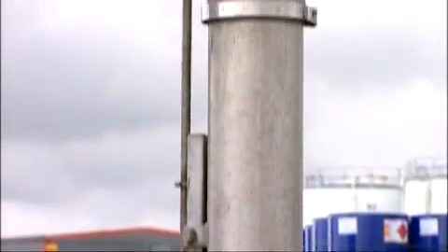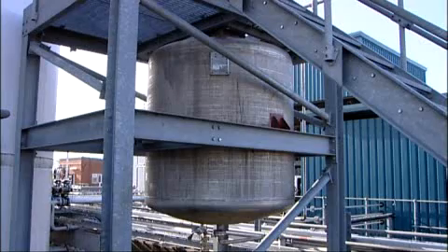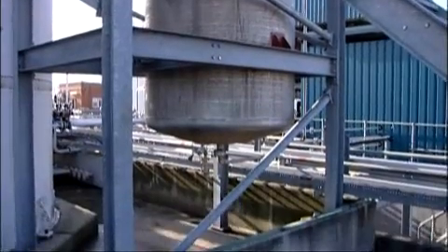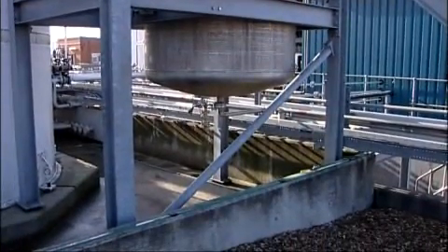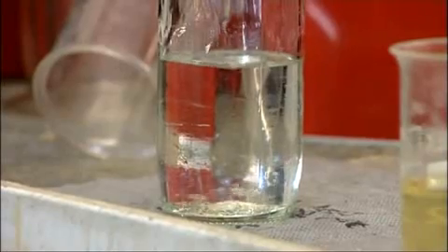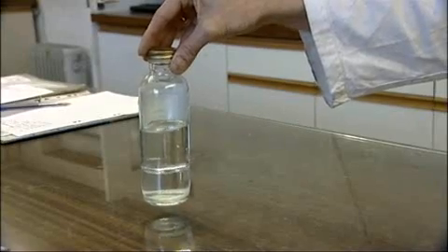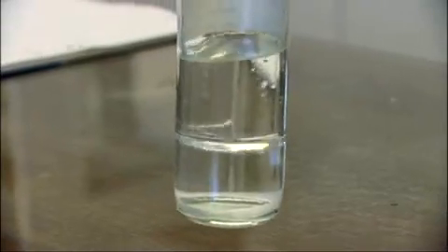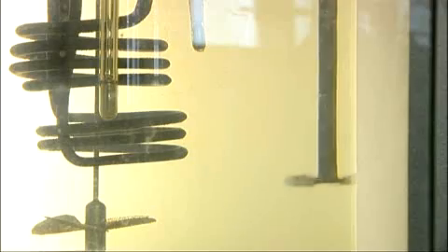Dispersing operations can be particularly hazardous in view of the extremely high rate of charge generation when particulates are present. High charge rates can also occur when liquids containing non-miscible components are mixed or agitated. With poor conductive liquids, the charge accumulation can cause sparking in the vapor space to an exposed agitator blade in a mixer or to a filling pipe.